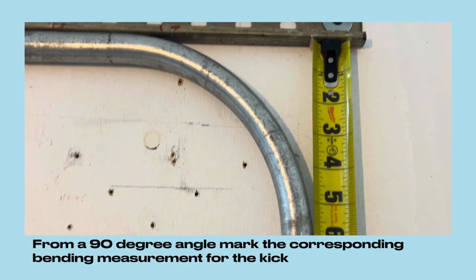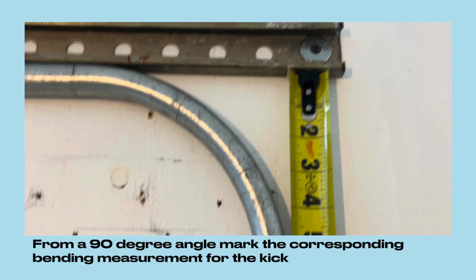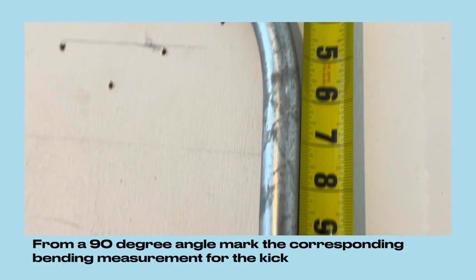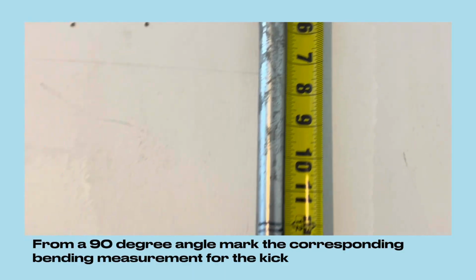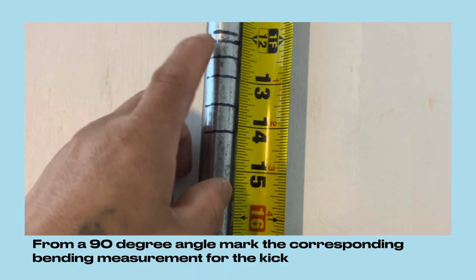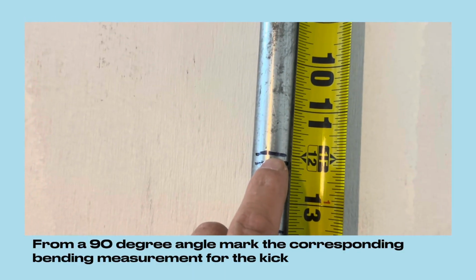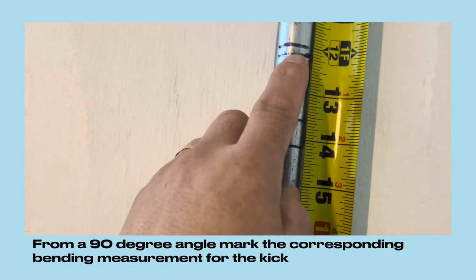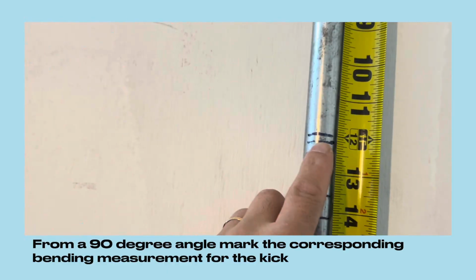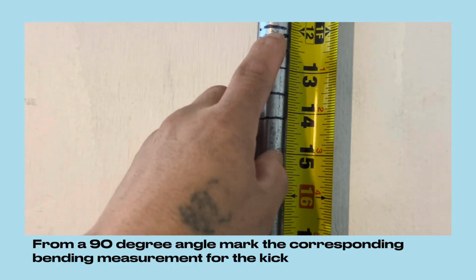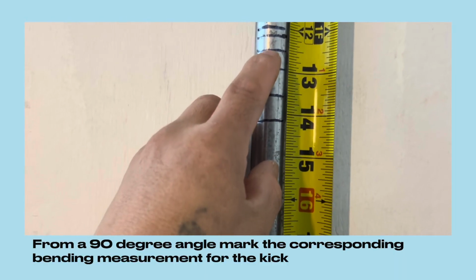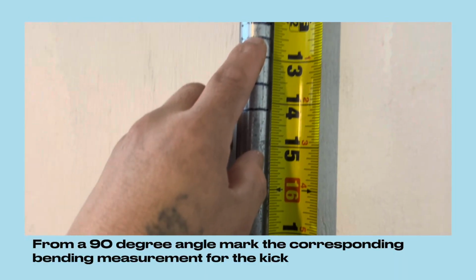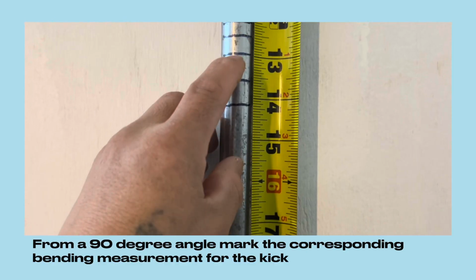And finally, you will mark the conduit from a 90-degree angle, and the first conduit will be at 12 inches, and the second conduit at 12 3/16 of an inch. Third conduit 12 and a half.